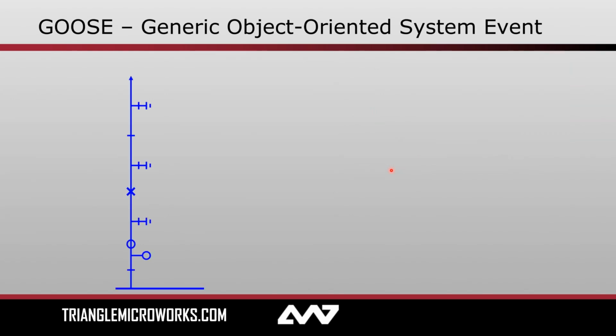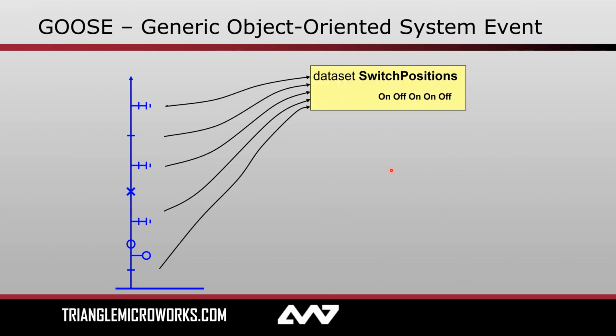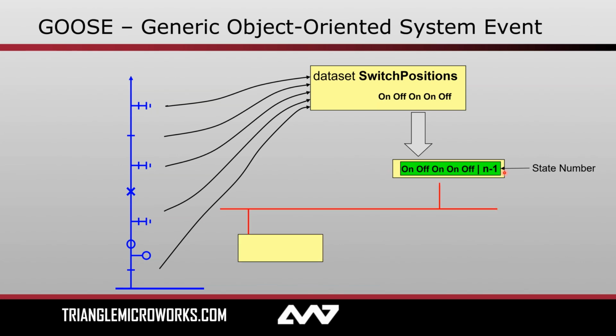So, let's take a look at an example and see how it actually works. I've got the same single line diagram that we looked at earlier, and a couple of different switch positions, which will come out of the data model of the IED that's interfacing with these different devices, packed into a data set. Those will be packed into a GOOSE message, which will be published out on the wire. And crucially, it will have a state number. I talked about how GOOSE has a built-in repetition mechanism to guarantee quality of service. State number falls into this category. So at my initial onset, I have these different values telling me my switch positions, and I have a state of N-1. This will be published out onto the network, and any subscriber that is configured to receive this GOOSE message will grab the relevant data out of it.